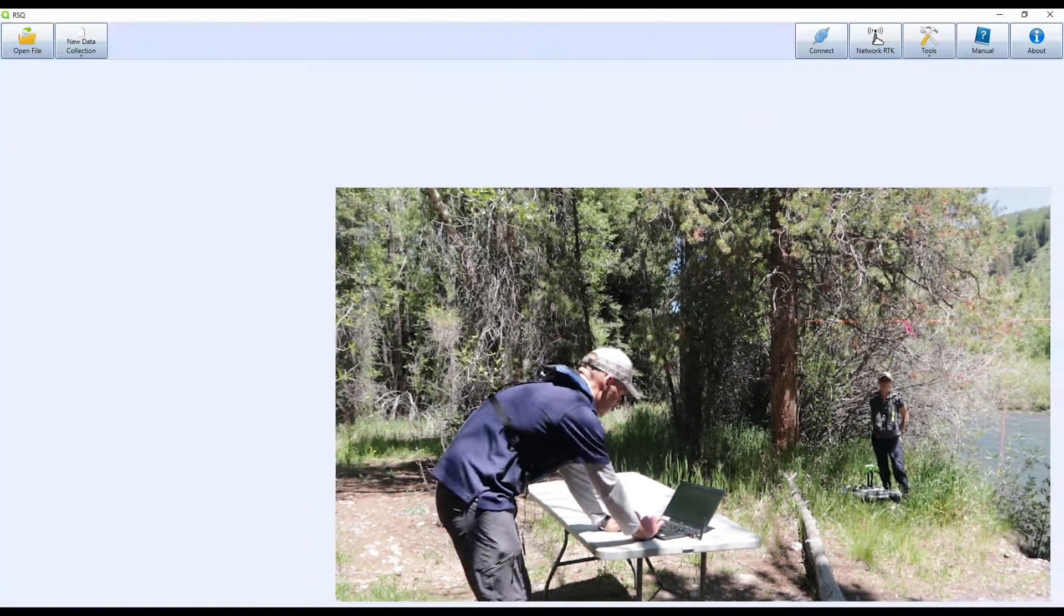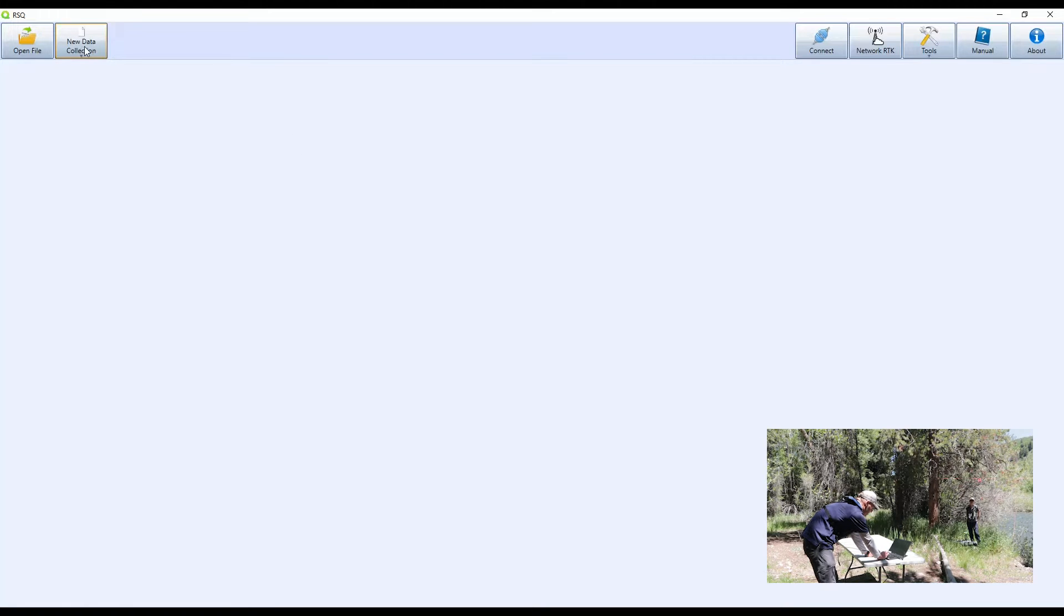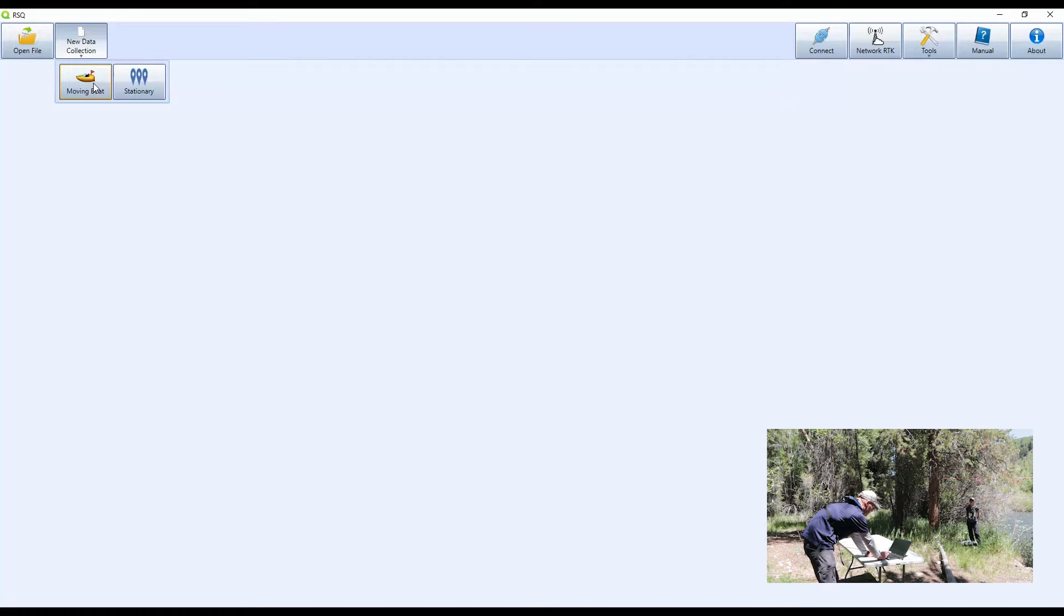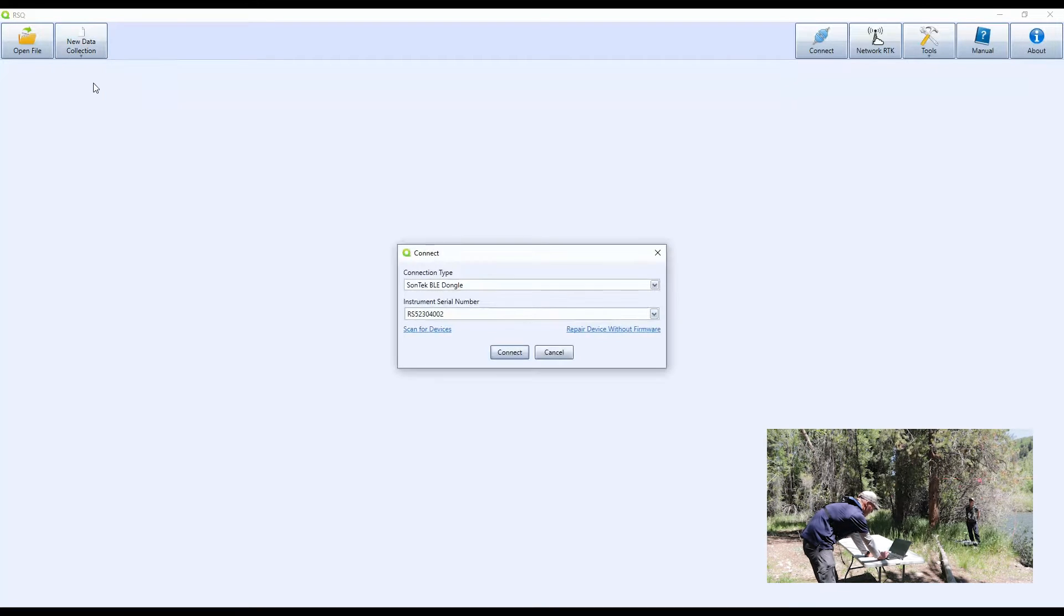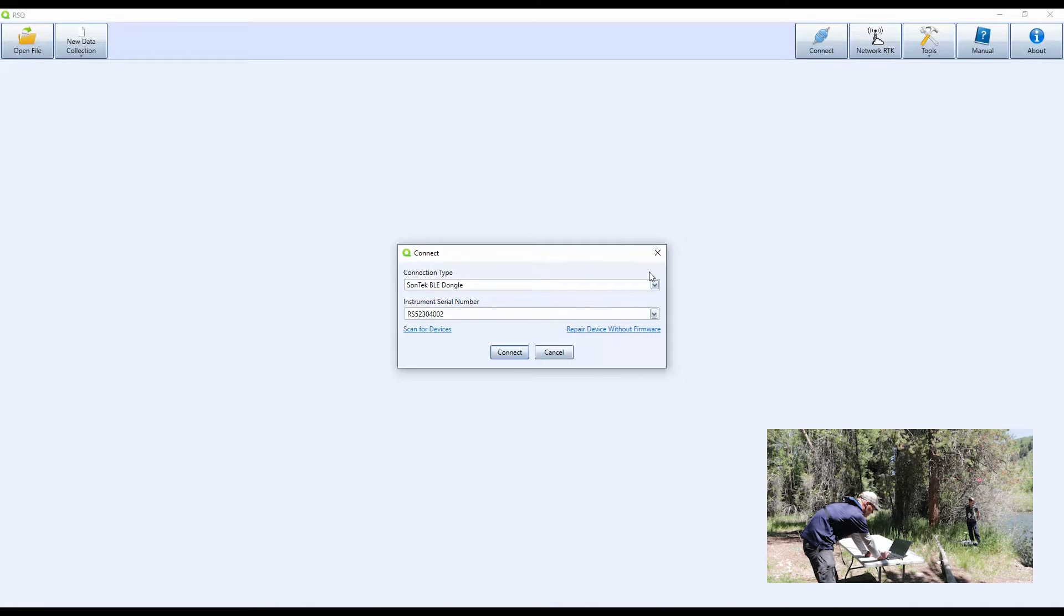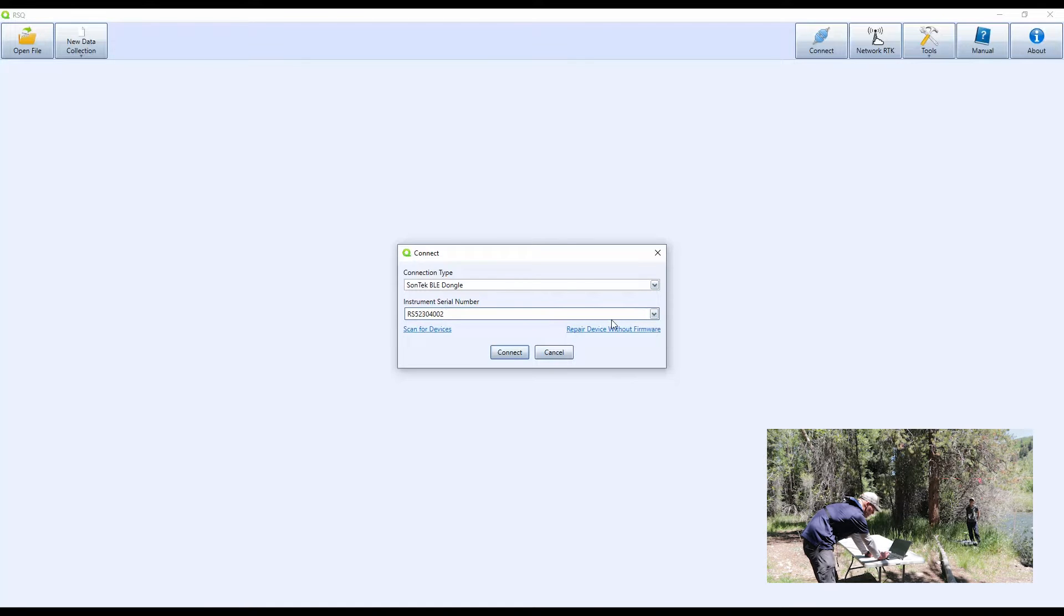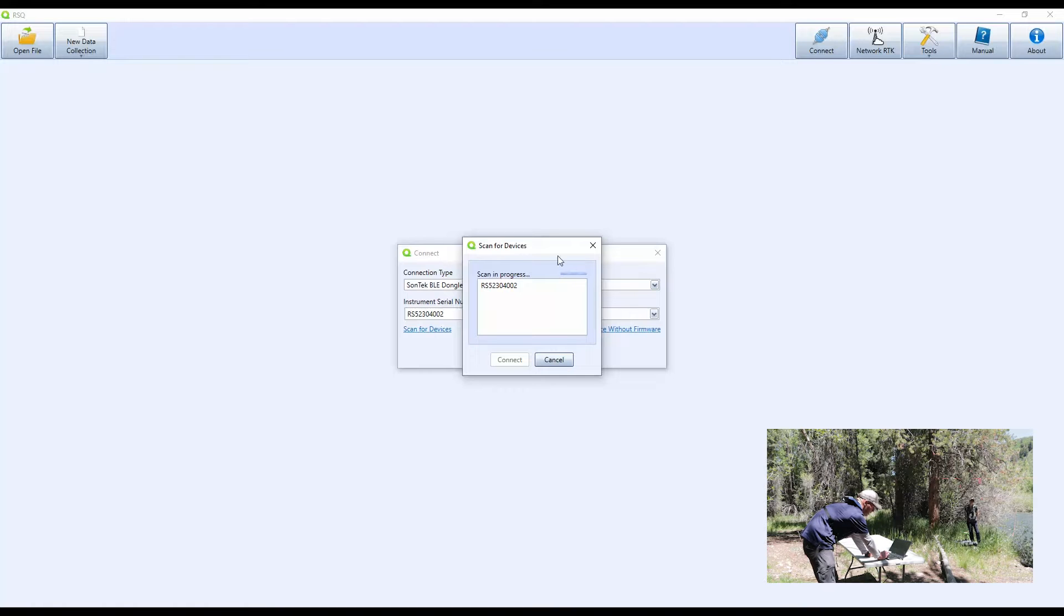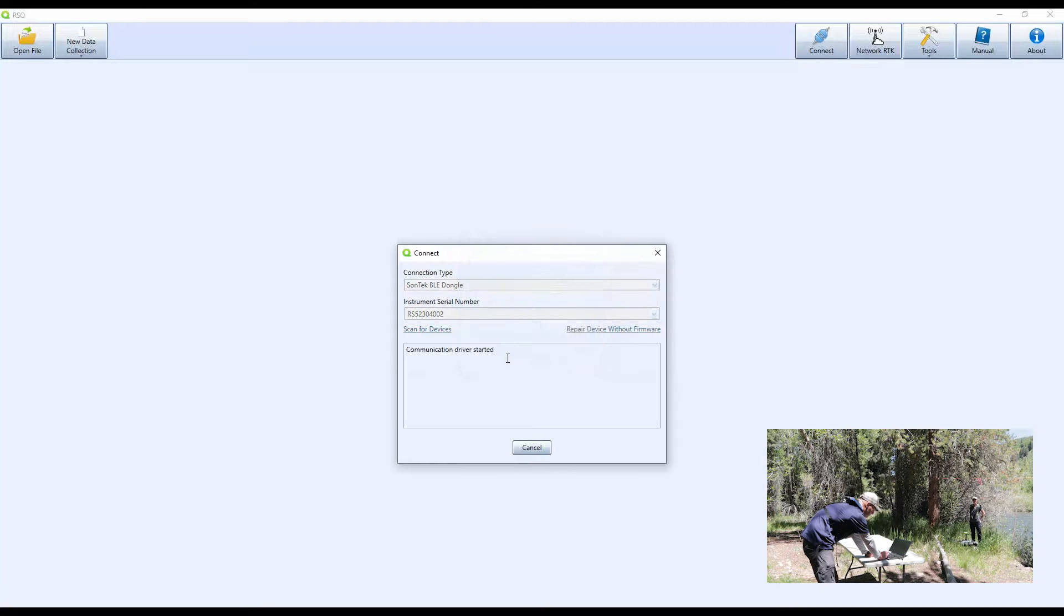First off, open up the RSQ software and then click on the new data collection icon, then select moving boat or stationary. For this case, we're going to be choosing a moving boat measurement. The connection dialogue will come up. Automatically it should show SonTek BLE dongle and then the last RS5 instrument you used by serial number, or you can click scan for devices and it'll show any that are on in the vicinity. So I'll pick this one because this is live and connected to it now.